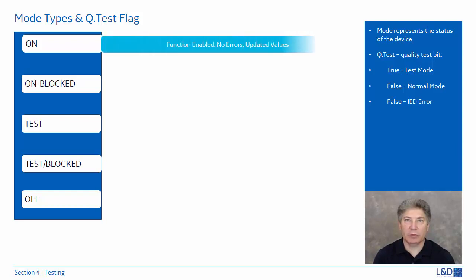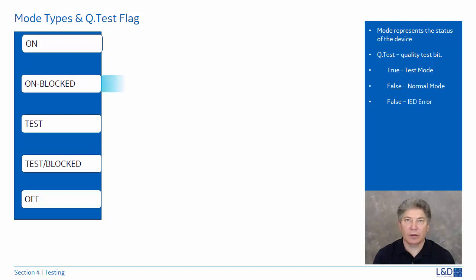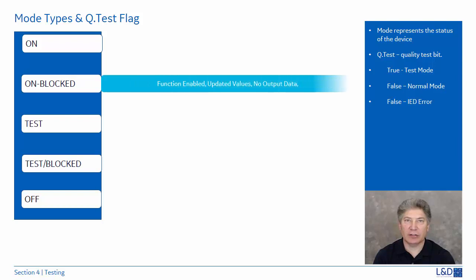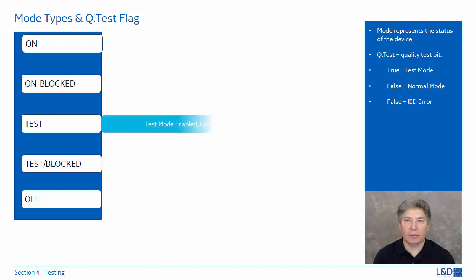On: the application is enabled, all communication services work, and we get updated values. The Q.test is set to false. The on-blocked status is where the application is enabled, all communication services work, we get updated values, but the element is blocked from operating. The Q.test bit is set to false. Next, we have test mode. This is where the test mode is enabled, we get updated values, the output data is controlled, and the Q.test is set to true. Next, we have the test blocked.